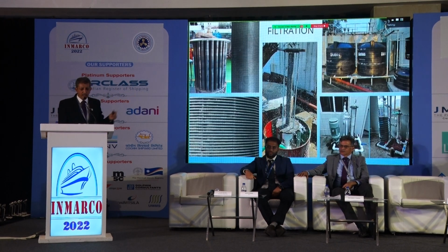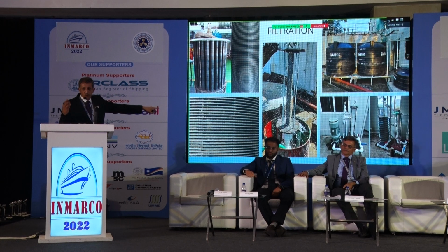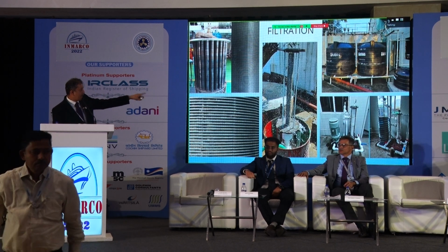What you see over here is the actual filter from the plant, which is ballast. From there, we took out one candle, and you can see the candle over here. This candle is the wedge wire. Each of the filter candles is properly cleaned. Since we are doing 3 runs, we took 3 candles, cleaned all of them properly, made sure that everything is flowing, and then we had a rig up.